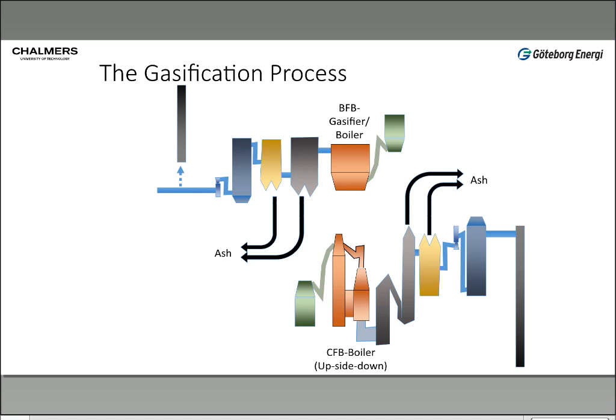To build a dual fluid bed boiler, you connect these two. The bed material that is heated and separated in the cyclone is transferred to the gasifier, and the fuel fed to the gasifier is converted as far as possible. The char that is not converted goes into the combustion chamber, producing the heat for the process.